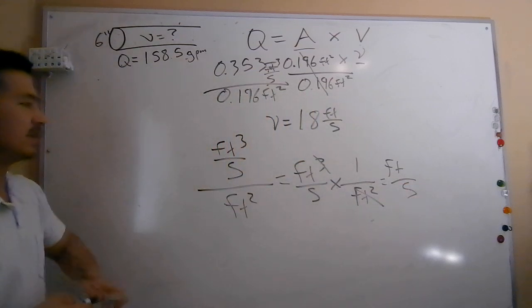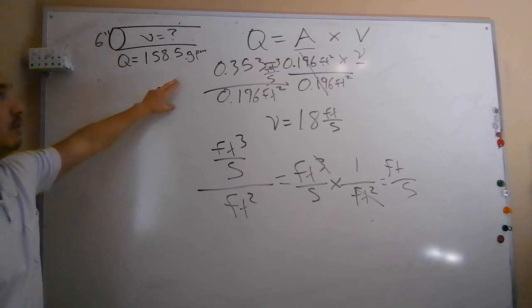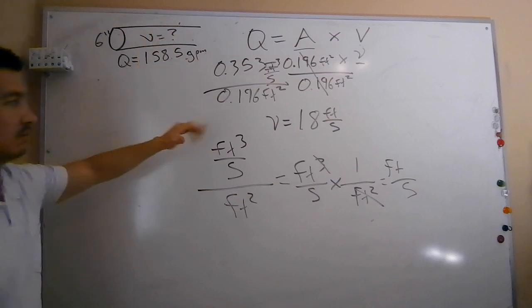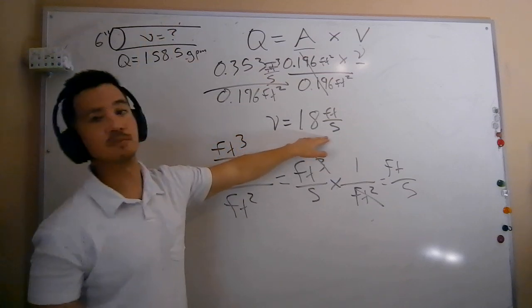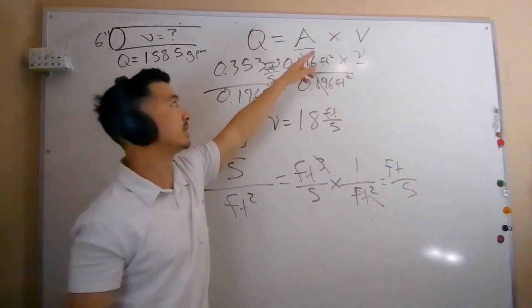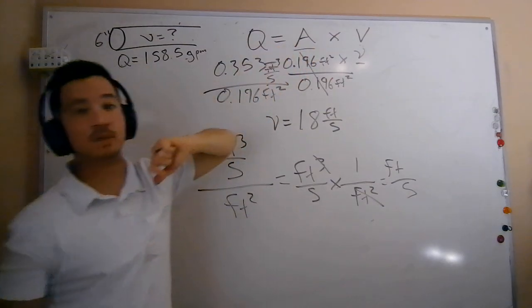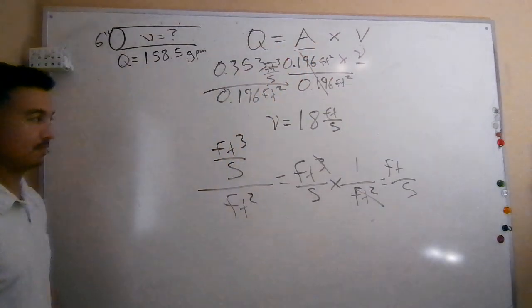Now you don't need to know the derivation of these units, but just understand when you're using the QAV formula, this is how you get from with a flow and an area to get to velocity. And the velocity you're going to get to is always going to be in terms of feet per second because your area is going to be in square feet and your flow is going to be in cubic feet per second.